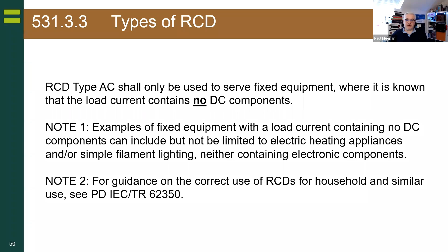And all it does is teach you how to figure out the sum total leakage of the circuit, because in that regulation there is a requirement to not overwhelm an RCD by 30%, which is about 9 milliamps on a 30 milliamp RCD. And all you do is you take the leakage of the connected appliances times by 0.75. So just using that table, if I had, worst case scenario, a printer at 1 milliamp, in theory I could have 12, times by 0.75 gives me my 9 milliamps. So that's how many I could have on that circuit to comply with the regulation.